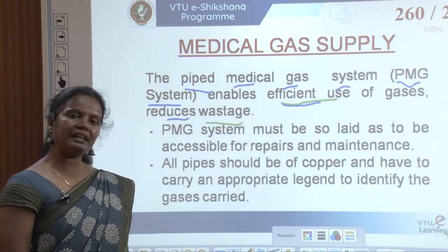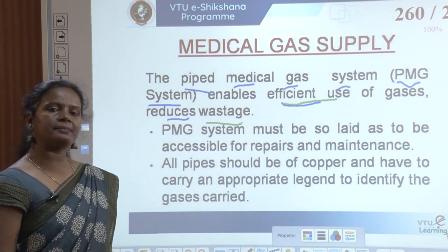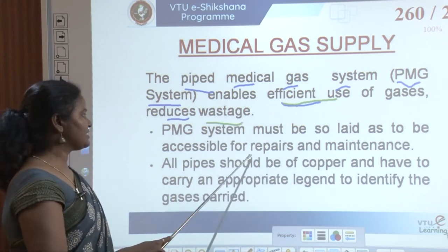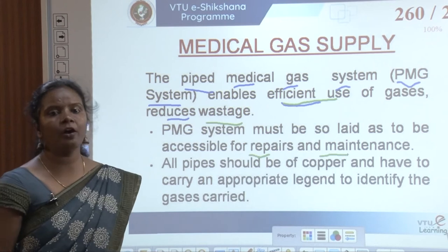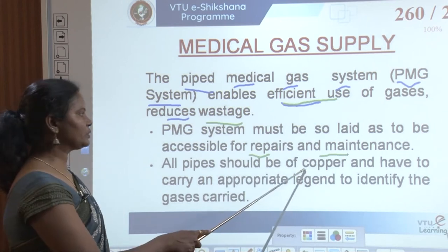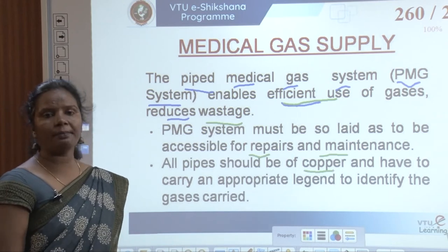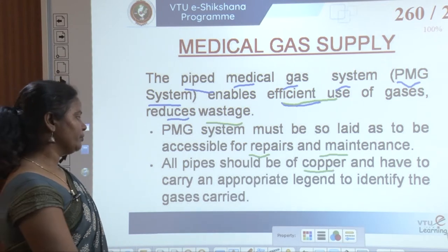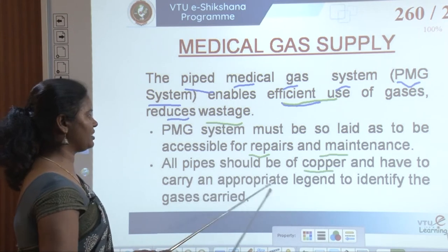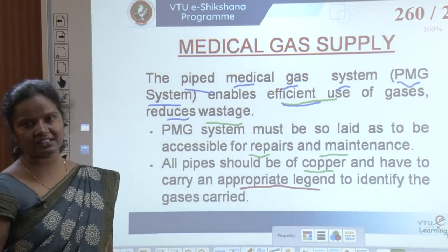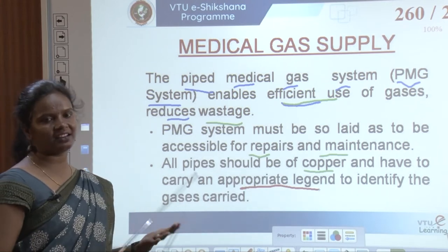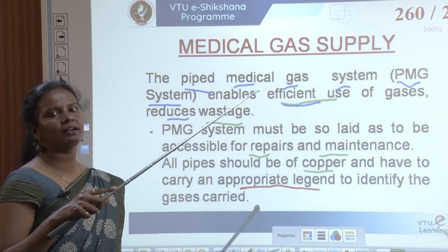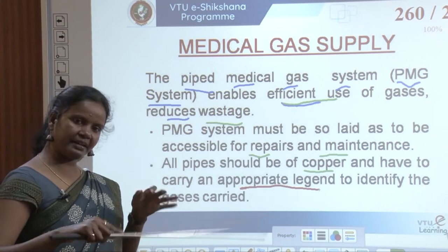PMG systems must be laid to be accessible for repairs and maintenance. All pipes should be of copper — this is mandatory. They must carry an appropriate legend to identify the gases carried. Color codes are used: all gases are color-coded and the same color-coded pipes are provided from the supply to the receiver points.